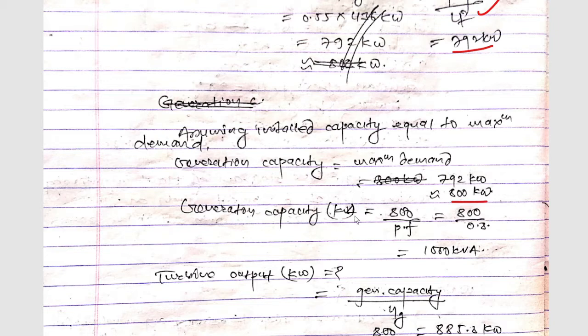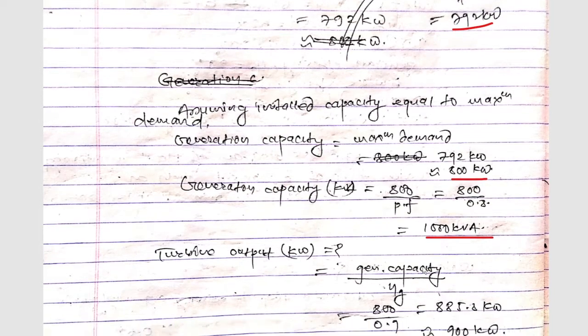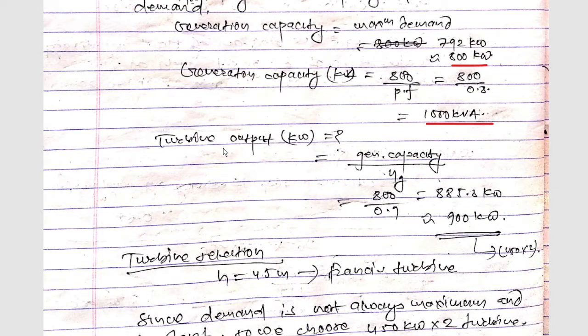So generation capacity means in KVA it will be 800 upon power factor, so 800 upon 0.8 which is 1000 KVA. And now turbine output will be generation capacity upon generator efficiency, so 800 KW upon 0.9 will get here 885.8 means that is equivalent to 900 KW.